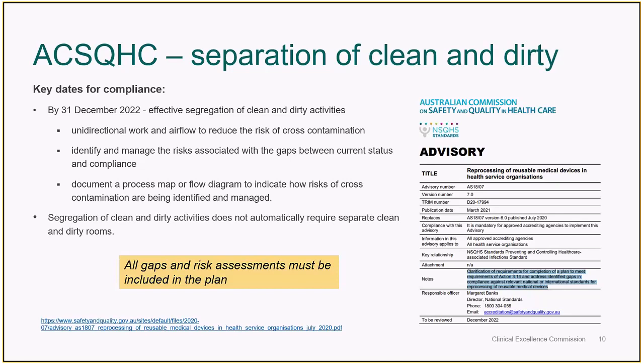And then you also need to document a process map or workflow diagram to indicate how risks of cross-contamination are being identified and managed. But segregation of clean and dirty activities does not automatically require separate clean and dirty rooms. For example, if you had a central sterilizing department, because of the standard requirements around air handling, and because the standard says you must have a demarcated decontamination area, you will need a separate room for decontamination.